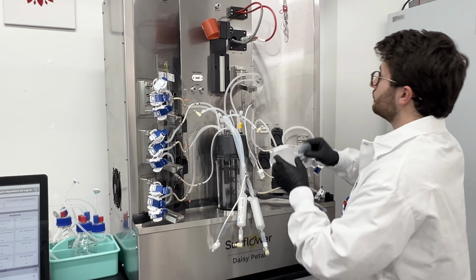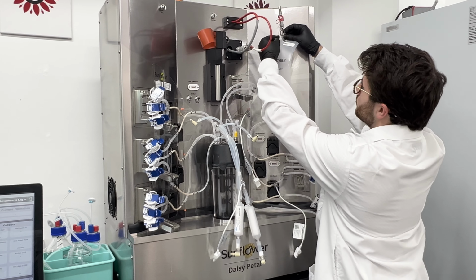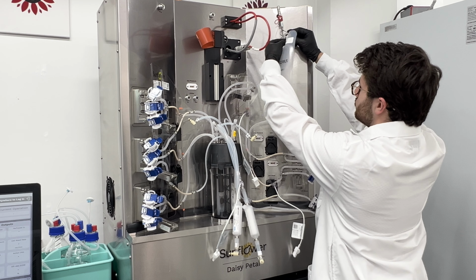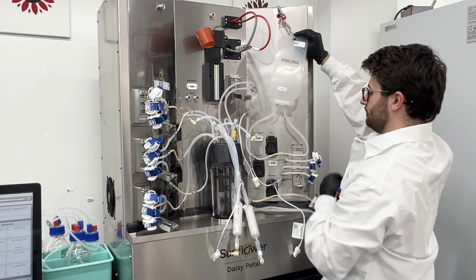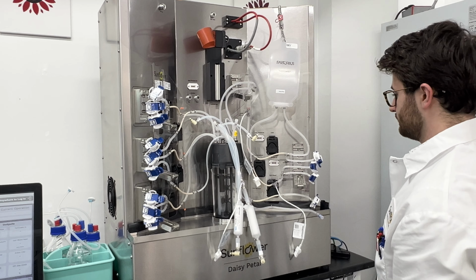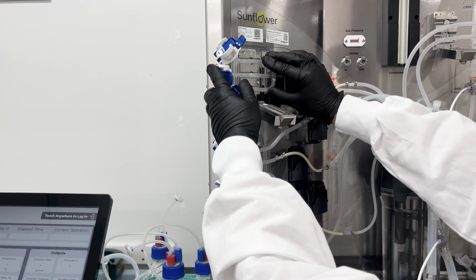Now we will hang the surge bag from the clip at the top of the right panel. Avoid pulling on the surge bag when installing it because this can damage the load cell that monitors the bag's weight during use. Next, we'll install the tubing into all of the valves.